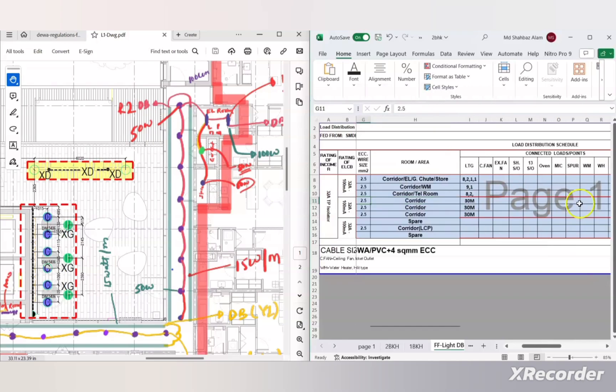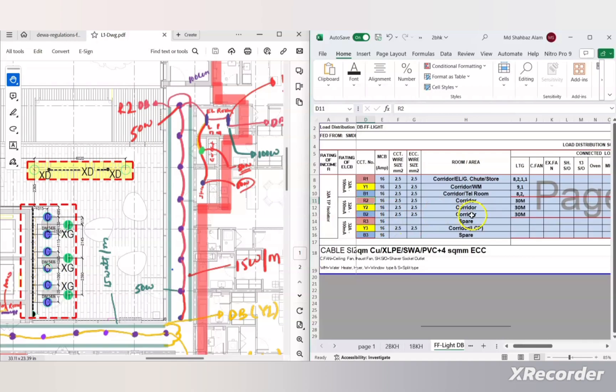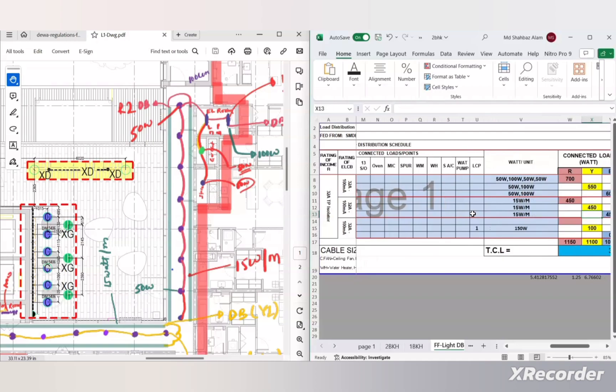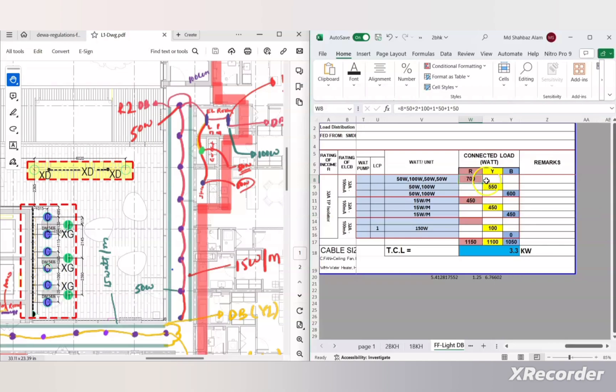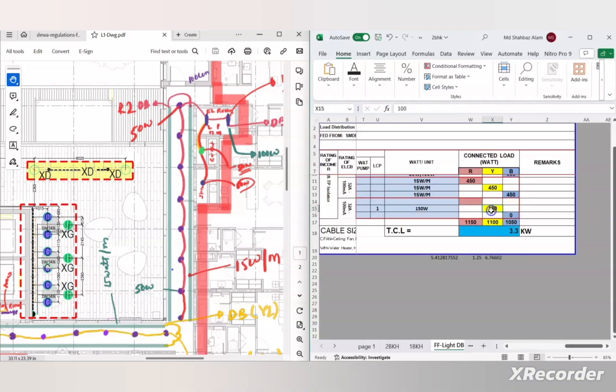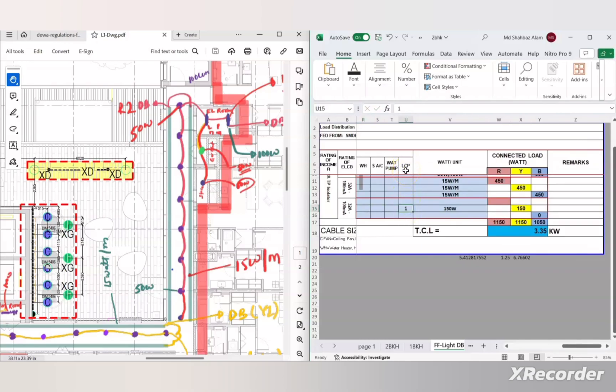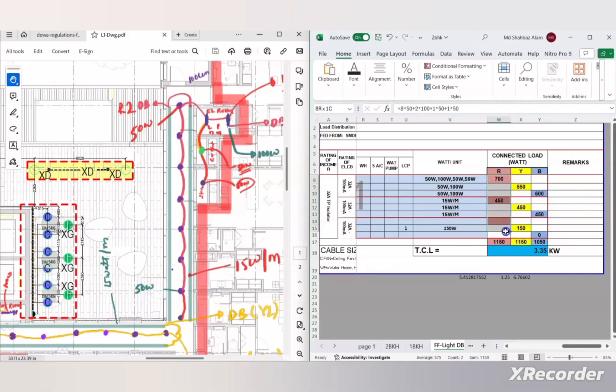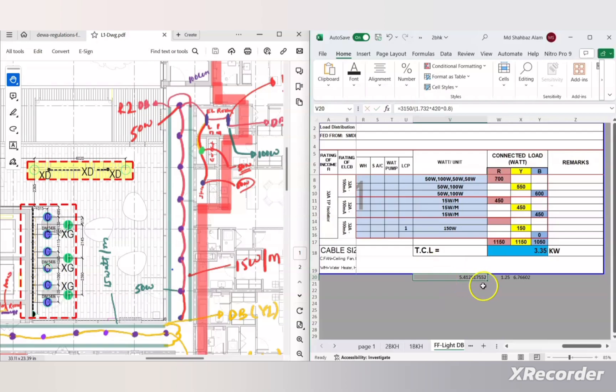In the same way, Y2 and B2 phases are done for the hidden lights. After writing all the loads, the total calculated values are: R1 = 700 watt, Y1 = 550 watt, B1 = 600 watt, and hidden lights = 450 watt each phase. There is also a 150 watt load for the LCP (Lighting Control Panel). The total load per phase: R phase = 1150 watt, Y phase = 1150 watt, B phase = 1050 watt. Total connected load on this DB is 3.35 kilowatt. The calculated current is 5.41 ampere, and with a safety factor it is 6.7 ampere.